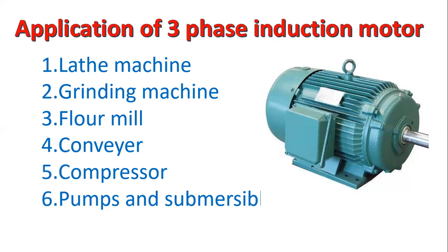Hence this motor needs starting torque. But this motor has the tendency to carry the starting torque, because it has a starting torque of 1.5 times the full load torque. So it can easily draw this type of load.